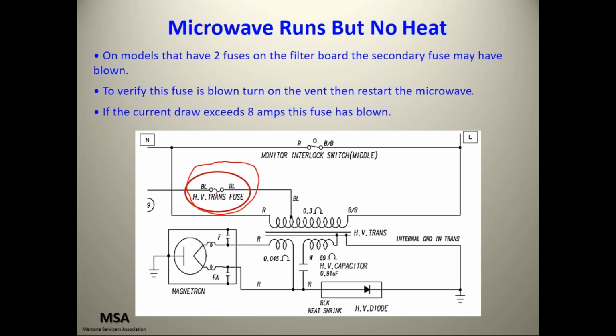Okay, this would be for high power. In other words, you're cutting some of the winding out of the transformer, so you're generating a higher current because that resistance, if you will, inductance actually, is higher. So your voltage is going to be a little higher, your output voltage. And that's done with this secondary fuse. If you want low power, or I should say if the board wants low power, they would energize the full winding of the high voltage primary.